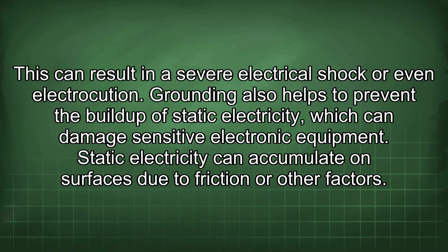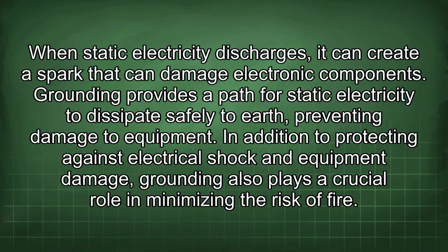Grounding also helps to prevent the buildup of static electricity, which can damage sensitive electronic equipment. Static electricity can accumulate on surfaces due to friction or other factors. When static electricity discharges, it can create a spark that can damage electronic components. Grounding provides a path for static electricity to dissipate safely to earth, preventing damage to equipment.